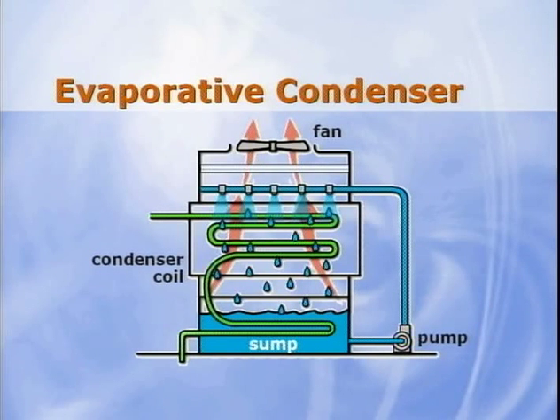Typically, moisture eliminators are placed between the condenser fan and the water spray tower and at the condenser air inlets to prevent water carryover. The water that evaporates in this process must be continually replaced with fresh water. As the water evaporates, the dissolved minerals and water treatment chemicals become more concentrated in the sump. To minimize the levels of concentration, water may be continuously bled from the sump with an equal amount of fresh water added. Additionally, in areas that have an inadequate or costly water supply, or if the use of water for the purpose of air conditioning is restricted, air-cooled condensers are favored over evaporative-cooled condensers. As mentioned earlier, the major benefit of evaporative-cooled condensing is higher energy efficiency.